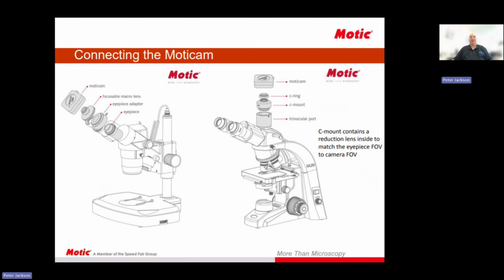Just to go back on that a little bit more. The ideal way to use a digital camera is to have what we call a trinocular microscope. So it's got 1, 2, 3 ports, and the C mount goes on and connects to the Moticam camera. If you don't have a microscope like that, or it is a non-Motic microscope, you can simply connect the eyepiece to the camera by using this adapter, which is included in the camera kit. And there's a focusable macro lens that lets you set it up properly. So this is essentially a universal way of mounting a camera onto a microscope. It's not anywhere near as elegant as mounting it this way, but you can connect the camera to basically any microscope. It's better to be done on a binocular microscope, obviously, because if you connect it onto a monocular microscope, then you can't see through the eyepiece whatsoever.